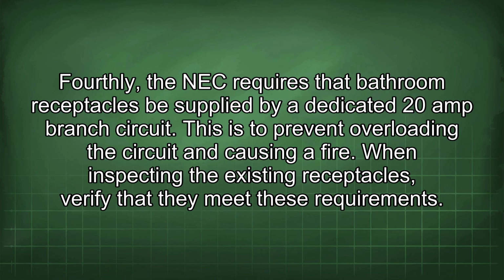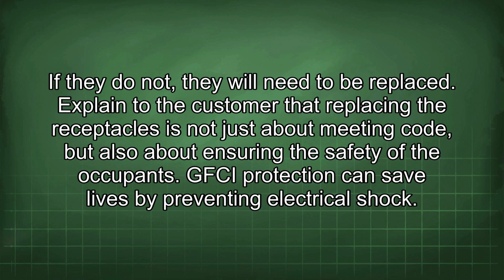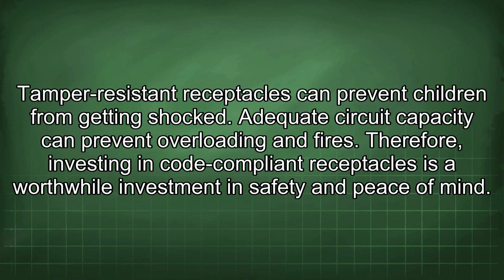Fourthly, the NEC requires that bathroom receptacles be supplied by a dedicated 20-amp branch circuit. This is to prevent overloading the circuit and causing a fire. When inspecting the existing receptacles, verify that they meet these requirements. If they do not, they will need to be replaced. Explain to the customer that replacing the receptacles is not just about meeting code, but also about ensuring the safety of the occupants. GFCI protection can save lives by preventing electrical shock. Tamper-resistant receptacles can prevent children from getting shocked. Adequate circuit capacity can prevent overloading and fires. Therefore, investing in code-compliant receptacles is a worthwhile investment in safety and peace of mind.